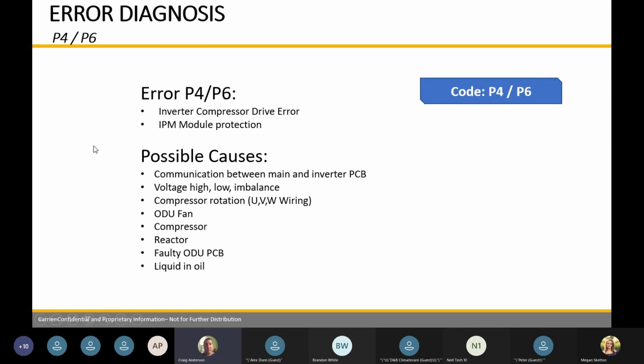And so error code P4, P6: inverter compressor drive error, IPM module protection, a bunch of things, communication between the main and inverter board, high voltage, low imbalance. That's your power going in. Is it fluctuating back and forth? Easy things that we can check before we go and check. We could have just a power fluctuation that's screwing everything up. Make sure the power coming into the system is constant, it's steady, it's not fluctuating around.